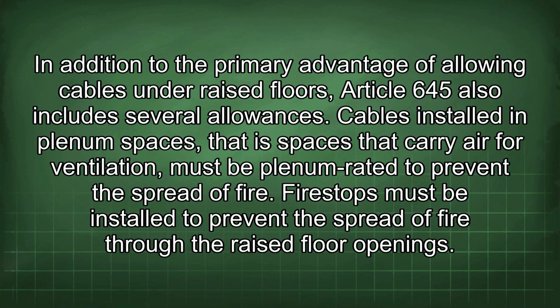In addition to the primary advantage of allowing cables under raised floors, Article 645 also includes several allowances. Cables installed in plenum spaces, that is, spaces that carry air for ventilation, must be plenum rated to prevent the spread of fire. Fire stops must be installed to prevent the spread of fire through the raised floor openings.